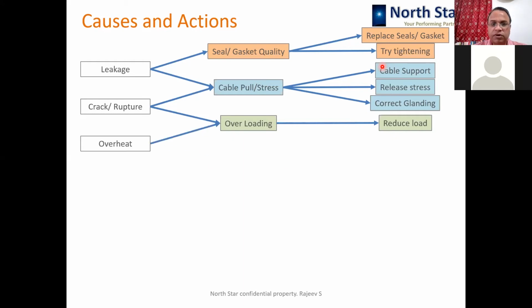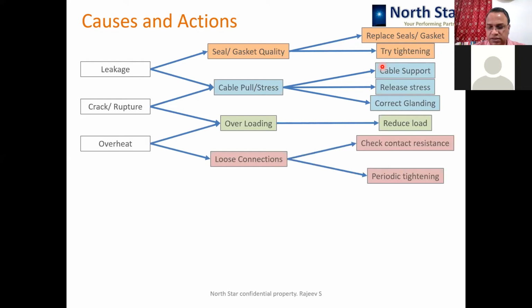Overheating happens because of overloading and loose connections. Ultimately, these loose connections cause high contact resistance, and as a result you get local heating, which causes the overheating. So checking contact resistance and periodic tightening is the solution. To check the contact resistance, thermal scanning can also be done, which can tell you which contact is deteriorating. There is another method which we recommend and suggest, which is our solution, which we'll be discussing at the end, and which can detect the poor contact much earlier than actual damage starts happening.